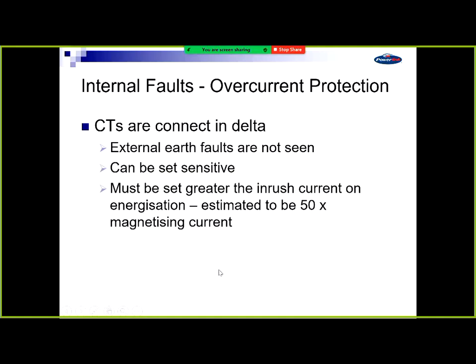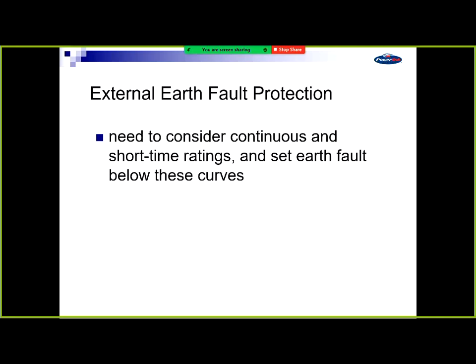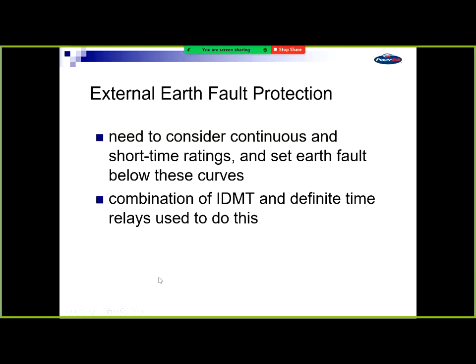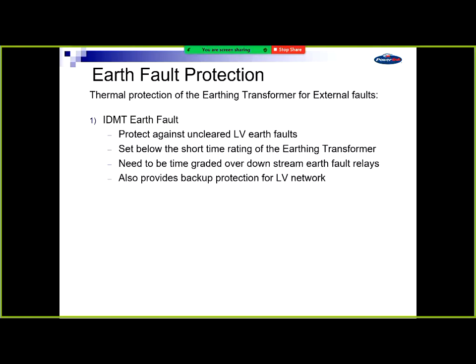So that's what that's really just saying there. We set it sensitive, but it must be set above the inrush and the magnetising current. And we usually use an IDMT curve for that. You need to consider the short time rating of the transformer and make sure that the earth faults are below that. And we use a combination of IDMT and definite time for the external faults. So the IDMT earth fault protects against uncleared external earth faults. It's set below the short time rating of the earthing transformer, it needs to grade over the top of downstream protection, and it provides a backup to the LV network as well. So just a level of redundancy.